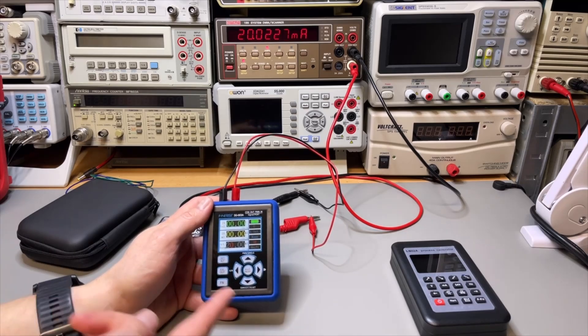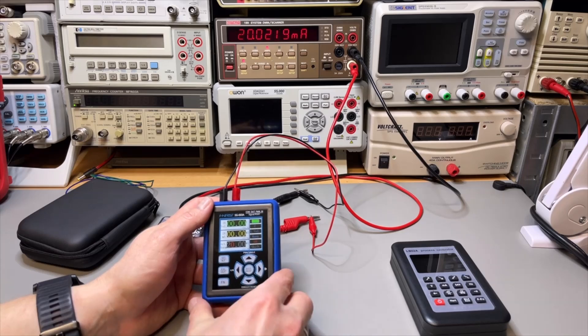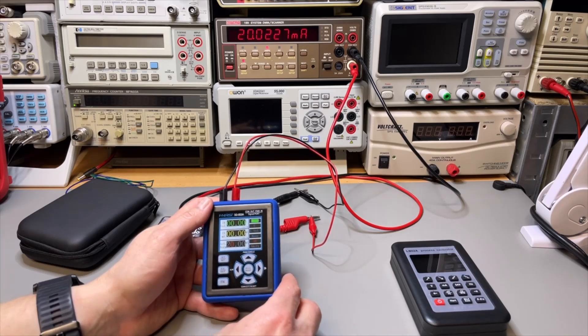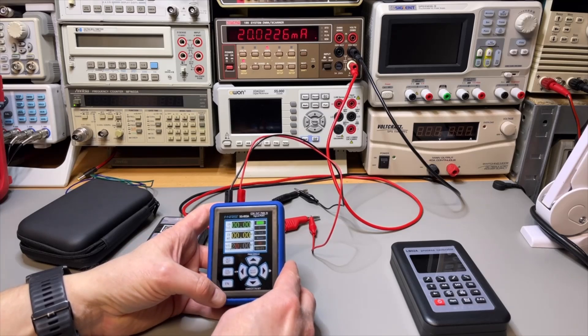It shows 4 milliamps. This is not bad at all. It goes up to 10, I think 11, no it goes up to 20. It should go up to 24 but again it is limited in the menu. I didn't manage to do that because you need to push a few buttons at the same time and it is just not that clear.